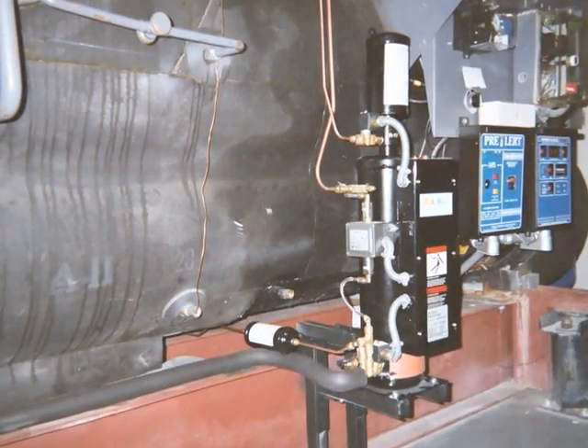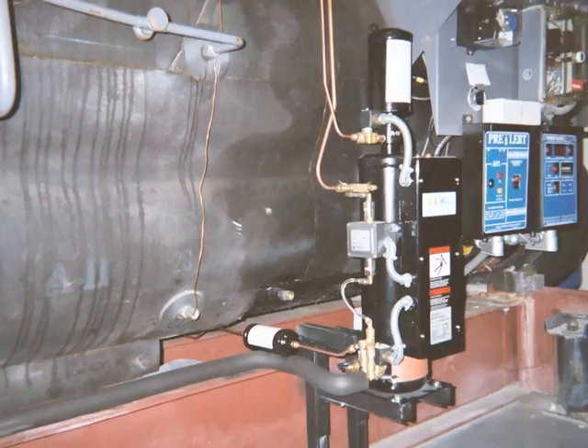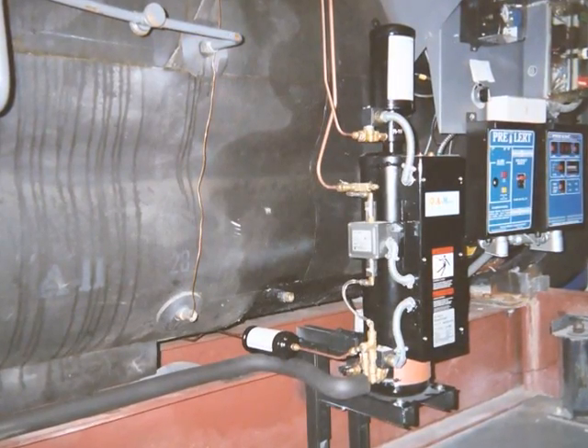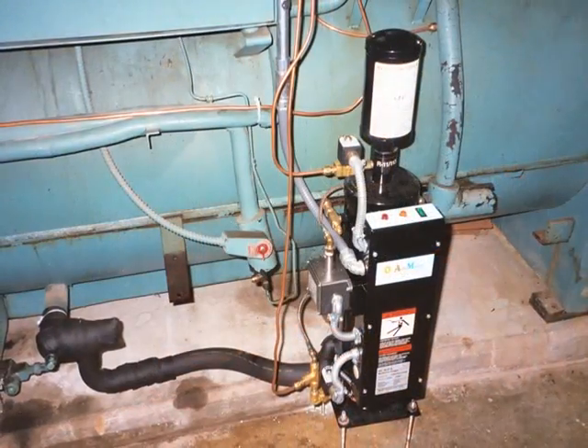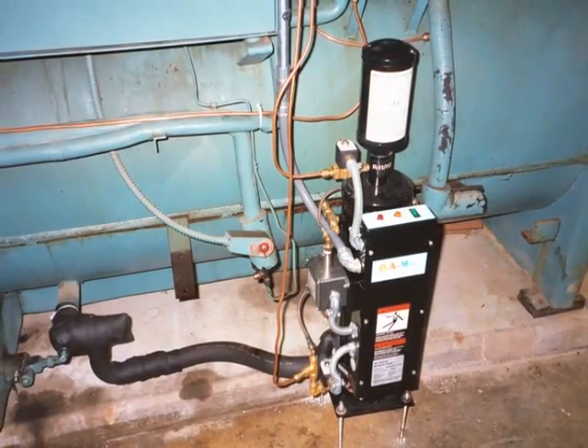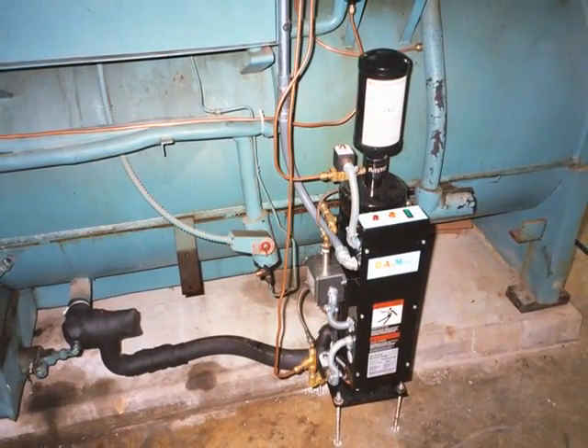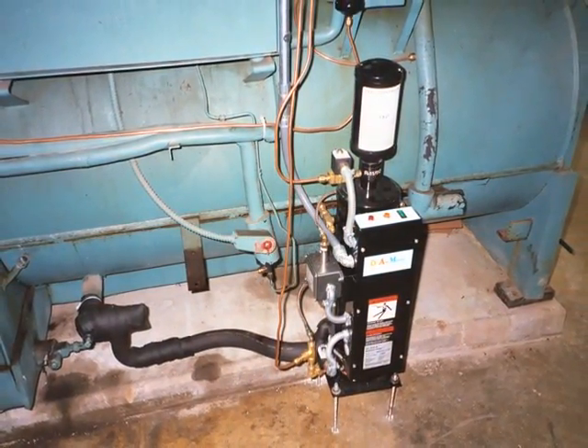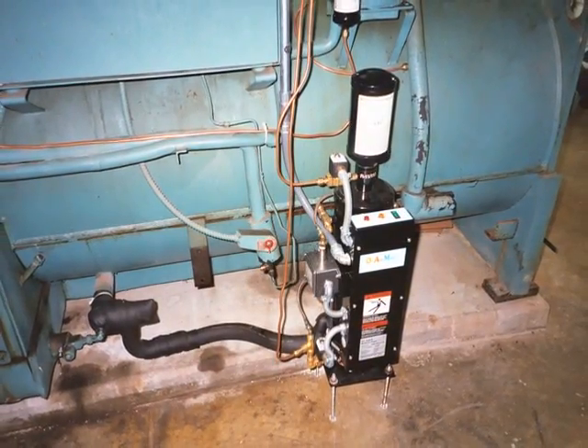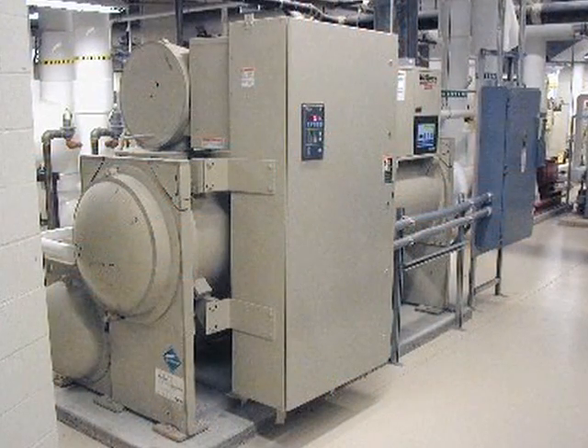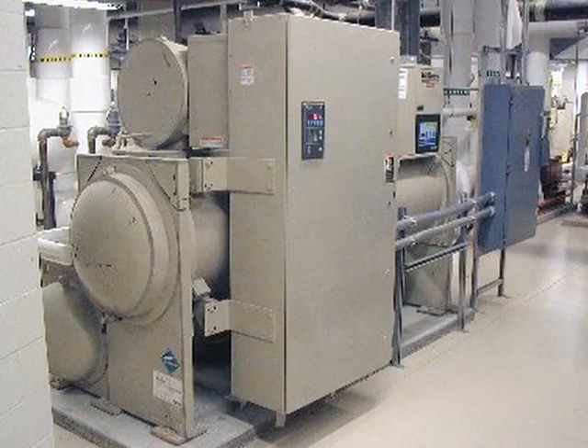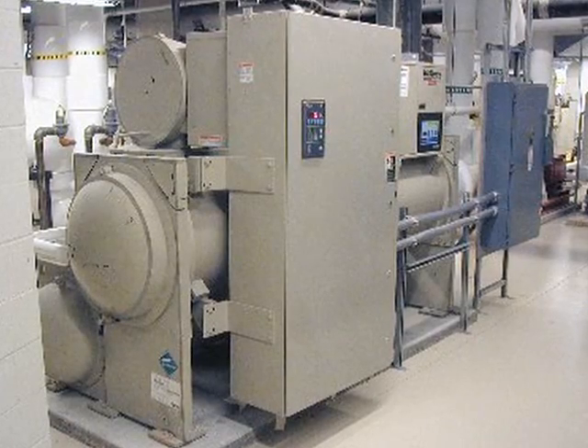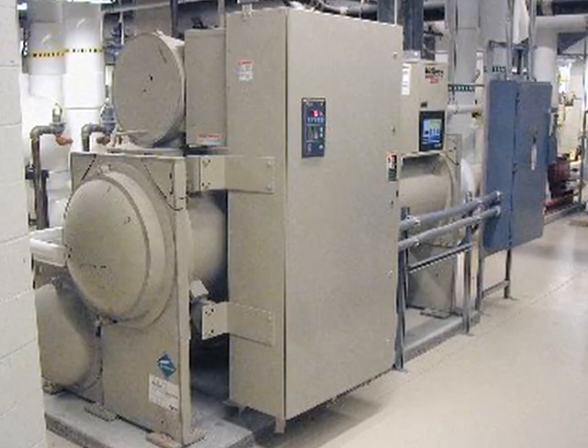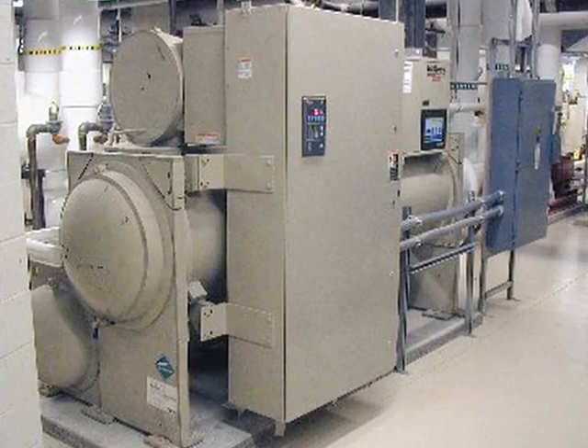Typically, there are three centrifugal chiller operating scenarios. Operating scenario type 1 are chillers that operate seemingly normal at full or near full load capacity most of the time, such as process chillers or air conditioning chillers in year-round warmer climates. Yet occasionally oil must be added to the oil sump. The question is why? Where has all the oil gone? The answer is it has migrated into the refrigerant charge in the evaporator.